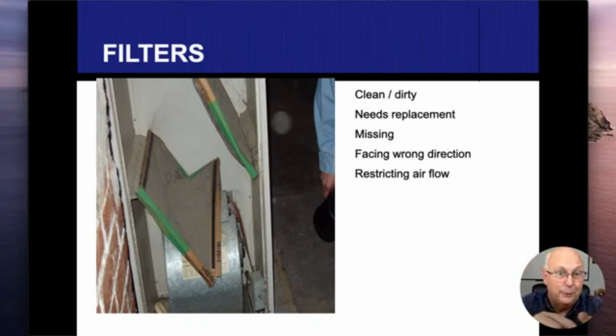So remember the order of airflow, going back a little bit. Filter, fan, heat exchanger, and then the air conditioning coil. Now that air conditioning coil, when it's running, creates a lot of humidity because the air inside is humid. That coil is cold. Condensation is going to form on it. If I'm blowing that dirt over that wet area, that's just going to create a cake of mud. And if it gets to the point, because there's no way to get in there without dismantling everything, that creates a cake of mud, then that's just going to stop my airflow. And now the only cure is to either take it apart and clean it, or remove everything and put a new air conditioning coil in there. Either way, it's not going to be cheap.